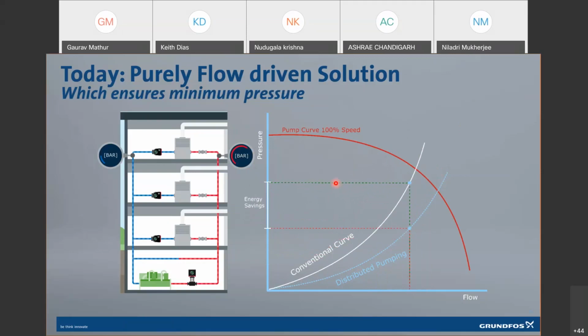And if you see this green dotted line as well as this red dotted line, the gap between these is the energy saving advantage which you have with distributed pumping. Now, what do you observe here? As the load is very close to the full load condition, you have lesser difference. But when the load goes down, when the flow requirements are less, that is where you have the maximum savings, even in some cases more than 50%. And that is a simple system curve way of looking at it. And this is where the energy saving is coming from. This is one of the areas where the savings are coming from.